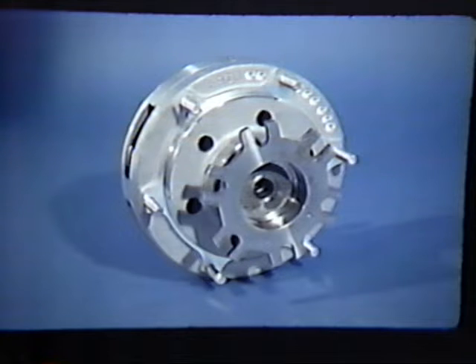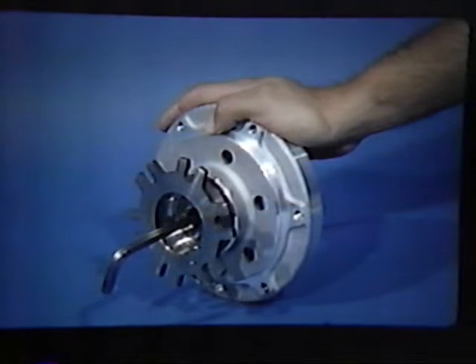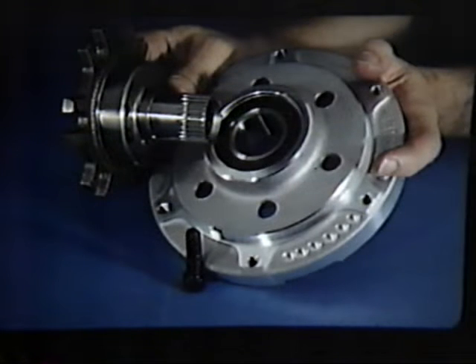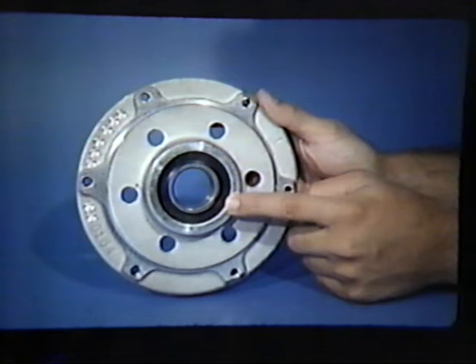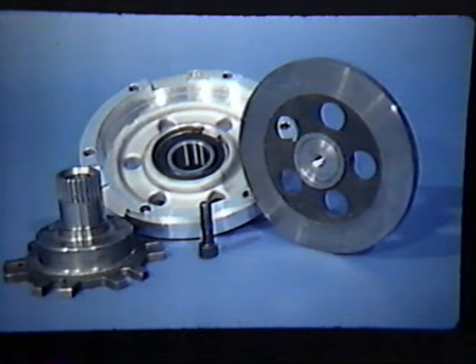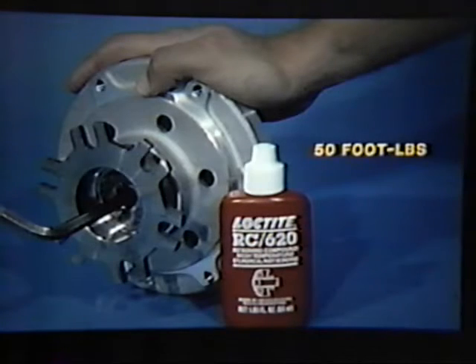If the drive sleeve assembly shows wear, replace it by removing the cap screw and disassembling the friction disc, mounting bracket, and drive sleeve assembly. Discard the worn drive sleeve assembly. Please note that the bearing is a permanent part of the drive sleeve assembly. Now, reassemble the mounting bracket, new drive sleeve assembly, friction disc, and cap screw. Apply Loctite 620 to the cap screw and install with a torque of 50 foot-pounds.